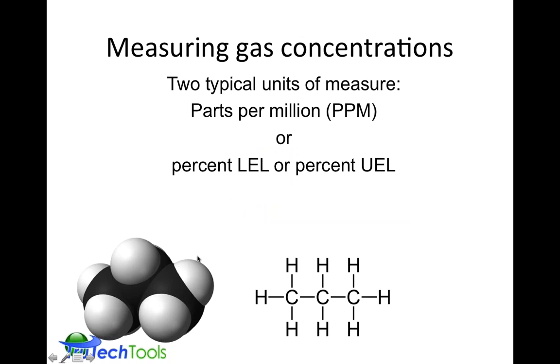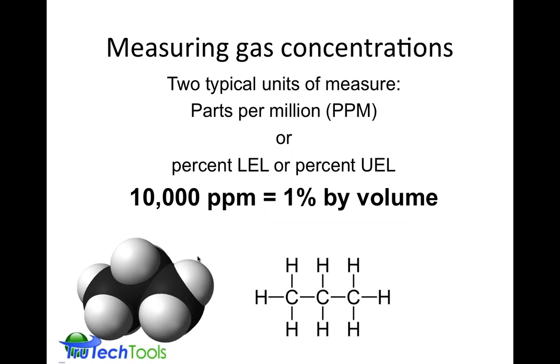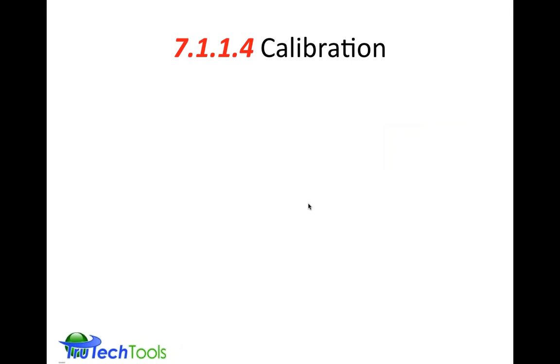So measuring a gas concentration is typically done in parts per million, or percent of LEL or percent of UEL. Now the actual gas concentration is specific to the gas, and percent gas is equivalent to ppm. There's an equation there between the two. But the LEL is different because different gases have different explosive characteristics. We talked about the 5% methane and 2.15% propane. Those are the lower explosive limits for those two gases. They are different. They will differ for different combustible gases.